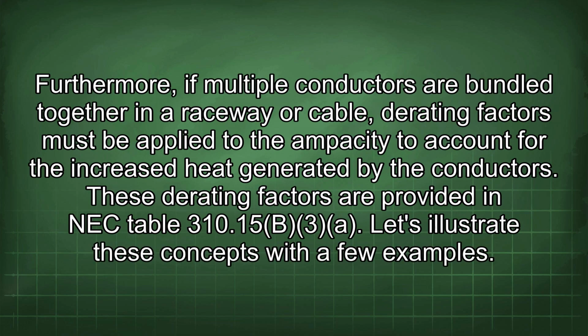Furthermore, if multiple conductors are bundled together in a raceway or cable, derating factors must be applied to the ampacity to account for the increased heat generated by the conductors. These derating factors are provided in NEC Table 310.15(B)(3). Let's illustrate these concepts with a few examples.